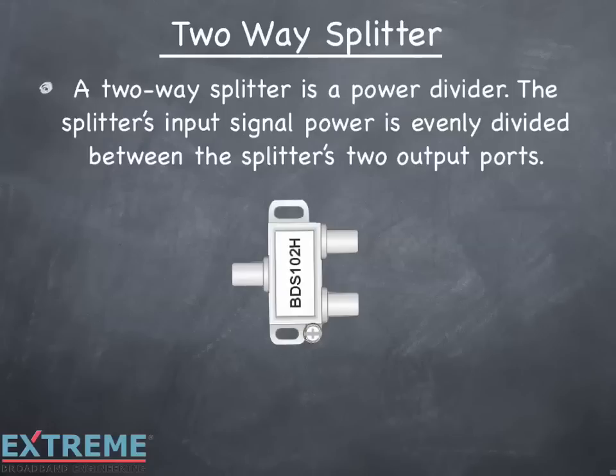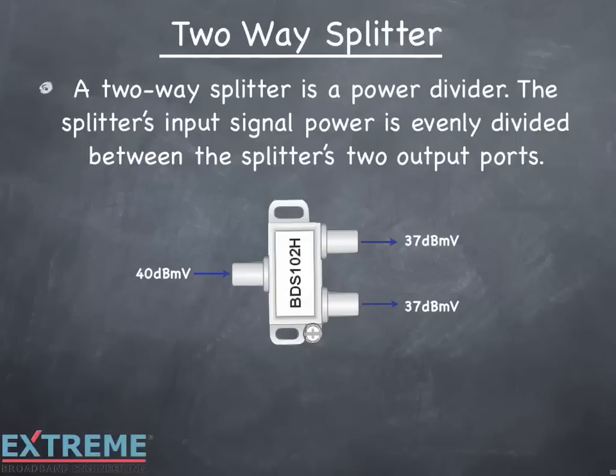A two-way splitter is considered a power divider. The splitter's input signal is evenly divided between the splitter's two output ports. If a splitter divides the signal equally, why when we inject a 40 dBmV signal into the input, don't we have 20 dBmV — or half the input signal — on both output ports instead of the 37 dBmV shown here? We have to look at the splitter from a power perspective.